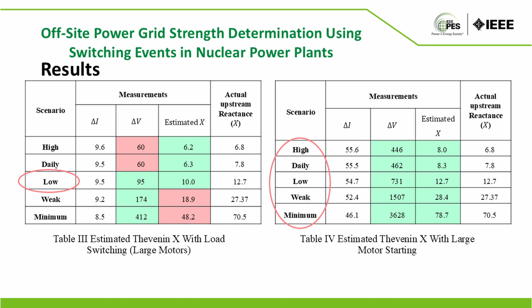Another type of disturbance was switching in loads rather than tap changing. When we switch in loads that are just active and reactive power, results aren't as good, with little overlap. But starting a motor, which is dominantly reactive, gives very good resolution in voltage magnitude and very good accuracy as well.